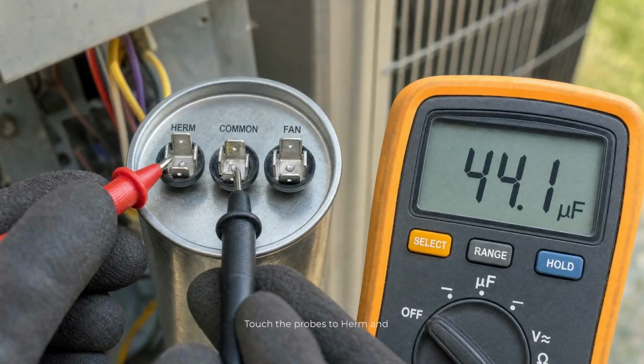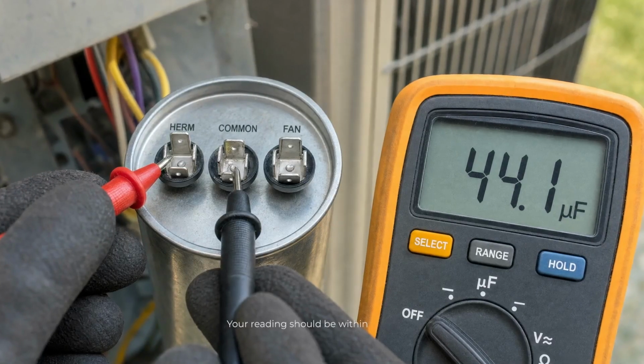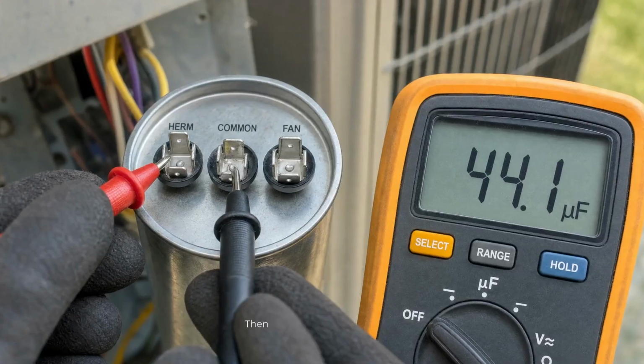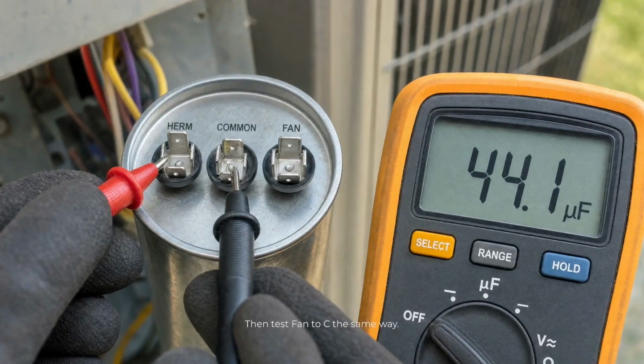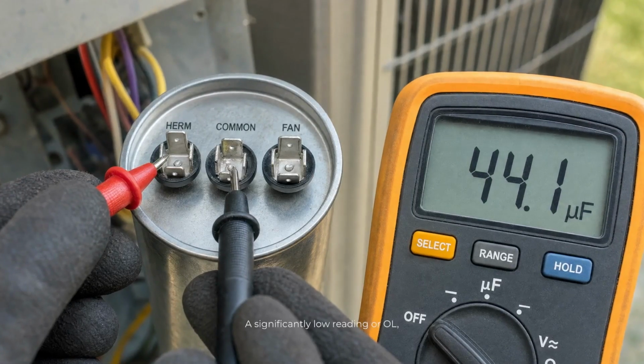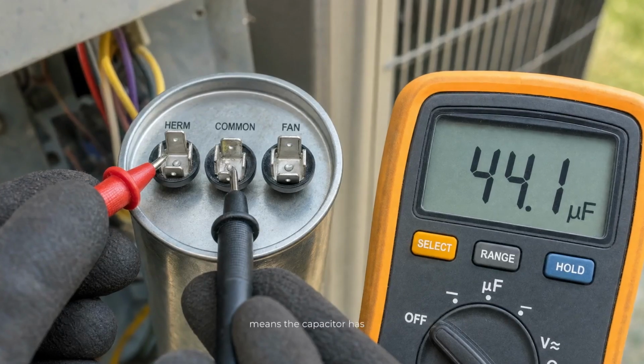Touch the probes to HERM and C. Your reading should be within about 5% of the rated MFD. Then test fan to C the same way. A significantly low reading, or OL, open loop, means the capacitor has failed.